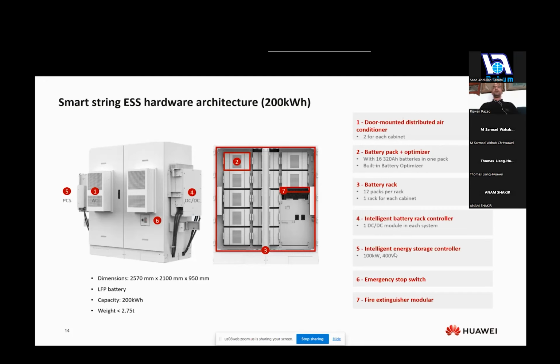So this is 16 units in total of the 320Ah batteries in one pack, and each one has its own battery optimizer. Number 3 is a battery rack. So in total there are 12 packs per rack and 1 rack per each cabinet itself. Section number 4 is your intelligent battery rack controller, which is your DC to DC module in each system in order to optimize the high voltage batteries. Number 5 is your intelligent energy storage controller, which is your PCS, typically known in the market. And this is at a capacity of 100 kilowatts in size and outputting at 400 volts.